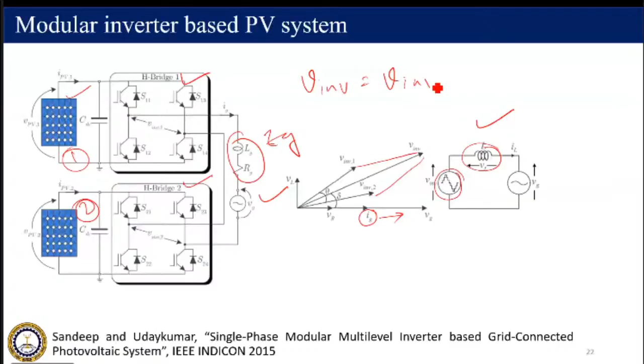This is the inverter 1 voltage and inverter 2 voltage phasor, and the phasor sum will be the overall inverter voltage. So V inverter is nothing but, since they are connected in series, V inverter 1 plus V inverter 2, the phasor addition. This is the angle delta by which the inverter voltage leads the grid voltage. Only if the inverter voltage leads VG does power flow from inverter to grid. Just like any synchronous machine, power always flows from a leading machine to a lagging machine.